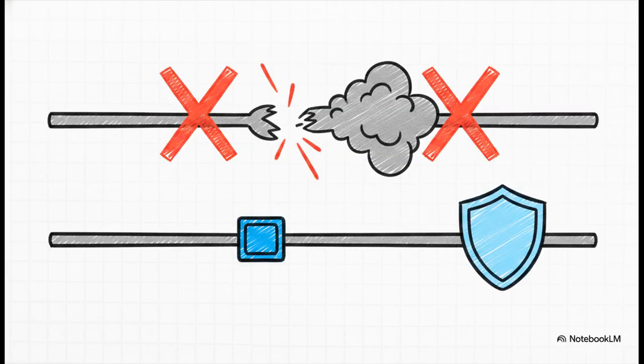The system keeps working seamlessly because full, identical duplicate frames are continuously sent over two entirely separate networks. Losing one complete network just means the receiver stops seeing duplicates. There is zero interruption to the actual protection logic or the continuous monitoring of the substation. It really is an incredibly robust solution.